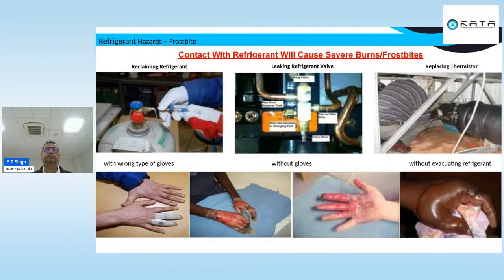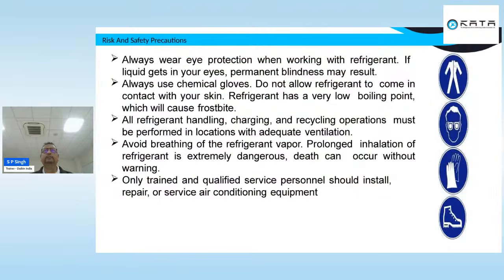Repeatedly I'm saying, use charging valves. Charging valves are available so that before you put your manifold gauge, you can put the charging valve, and after putting it, you can rotate it clockwise or anti-clockwise, open or close it, so that very little refrigerant can escape or hit your body. We should take care of this.